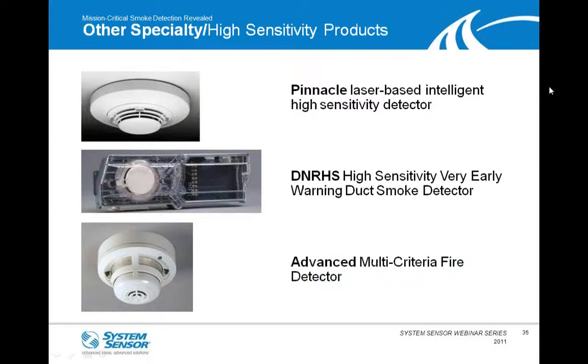So in addition, more specifically, some of the other products that are very conducive to the mission-critical type facilities that need this early warning or very early warning is our Pinnacle laser-based and intelligent high-sensitivity spot detector. Again, that does give you that point ID. So if you have a certain area or maybe a certain piece of equipment, maybe you don't want to use aspiration there, or maybe you want to use aspiration in the general area, but then directly on or above that piece of equipment, if it's super critical, you can have an addressable spot laser-based detector that gives you that point ID to know exactly, rather than just a general zone, where that condition is, and go and mitigate that risk.